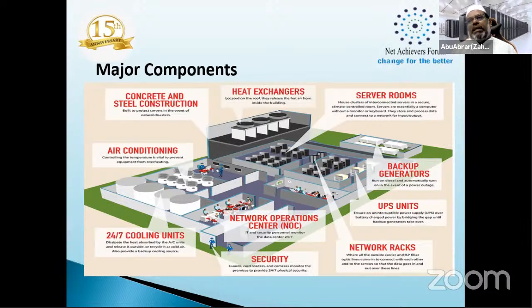Nowadays there are modular data centers. For example, if you have a 500 kVA UPS, instead of having it in one unit, you can have modules, like 100 kVA modules, across 4 or 5 slots, and another set of modules in another system. So you have redundancy within the system, or we can have another arrangement. I'll discuss all that later, inshallah.